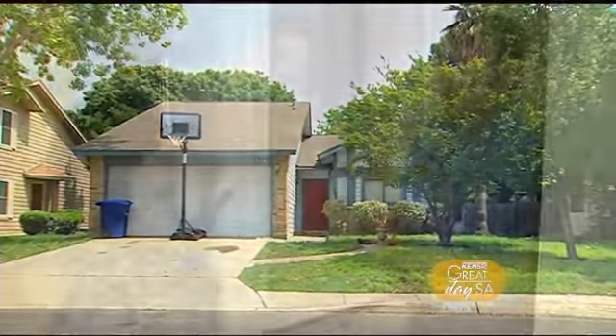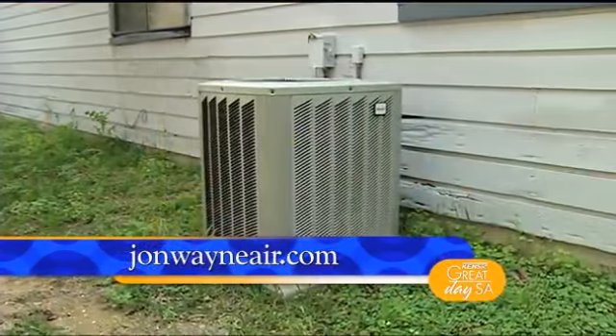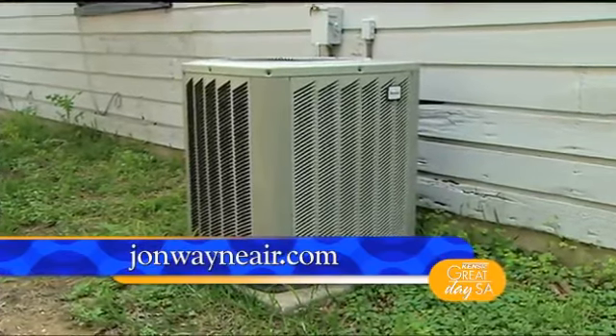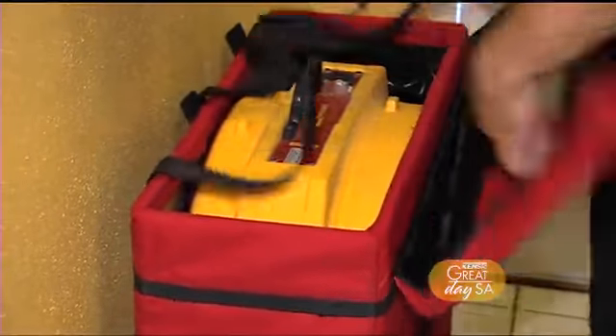As you know, we looked at your house the other day and noticed lots of problems. One of the things I noticed right off the bat is that I believe you do have an oversized system. We were talking about that earlier, why you have high humidity and say you have to lower that thermostat to feel comfortable. It's not because of the temperature, it's not because you're hot, it's really because you're wet. The house is very humid. You can walk in this house and feel the humidity levels are probably high all the time. And that's typically because the system is oversized.